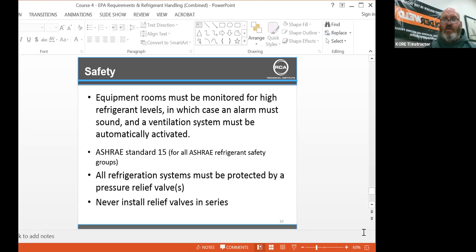No, it's really loud. I had a pressure relief blow in Southern California. It was in the motor room. I took the technician's word for it that everything was working properly. He'd actually jumped out some safety switches that I didn't know about as we were charging, and we exceeded the pressure in the receiver. Again, I took his word for it, and I blew probably a couple of 100 pounds of R22 until the pressure relief reset. We had to pull all the gas out, isolate the receiver, and replace the pressure relief, because this pressure relief did not have the little front seating valve on it. It was actually screwed right into the top of the receiver.